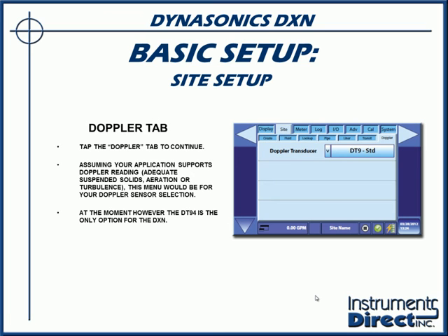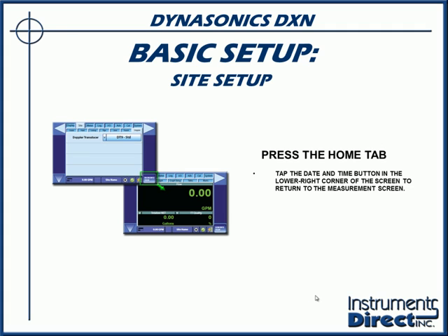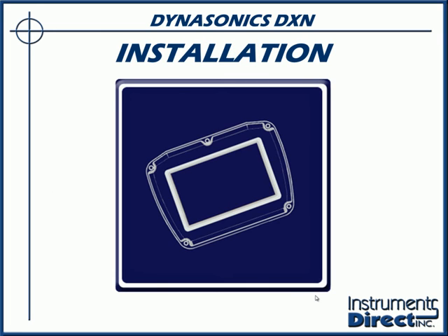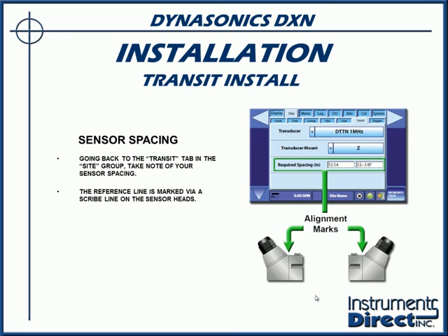If you want to use the Doppler tab, the Doppler is not sensitive to spacing. You would specify the Doppler transducer and you'd be all set up. So when we're done at this point, we're just going to press the Home tab and go back to the main screen so we can begin to read our data. We'll be able to monitor your flow rate and total flow. Now, as far as installing the device, well, we just got the spacing for the transducers. On the transit time transducers, you will note that the dimension is not from butt end to butt end here.